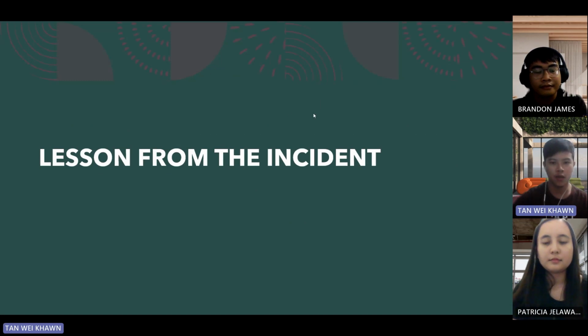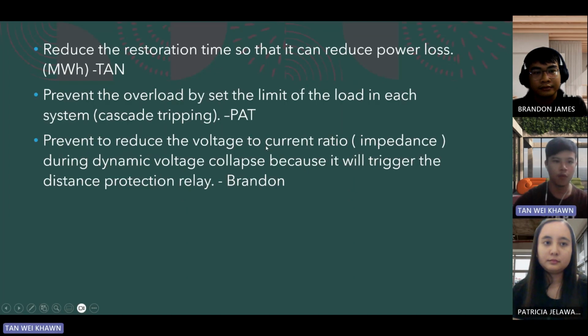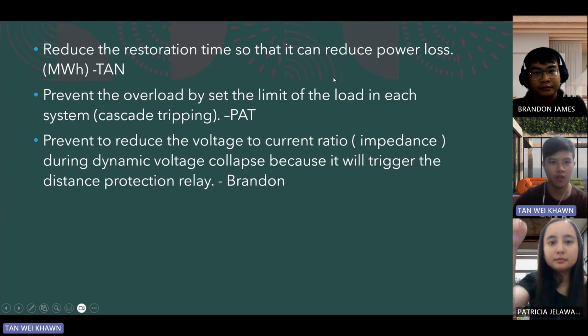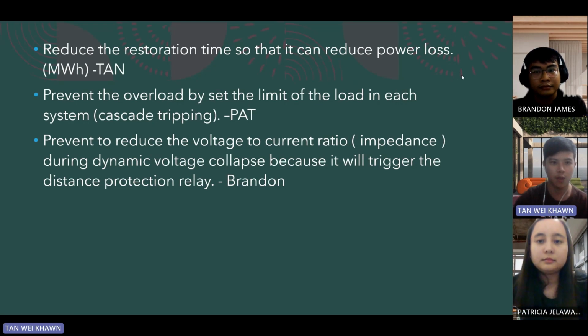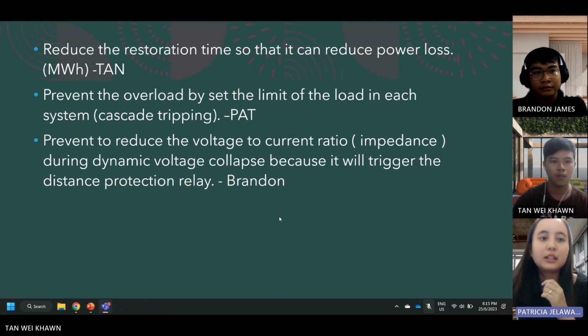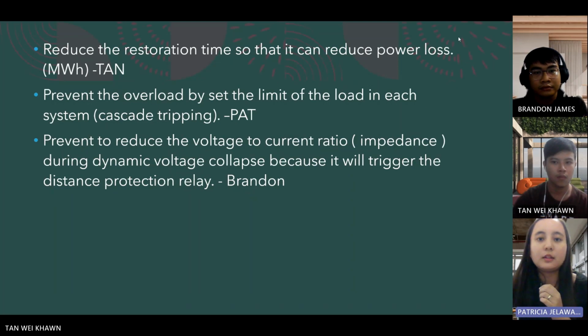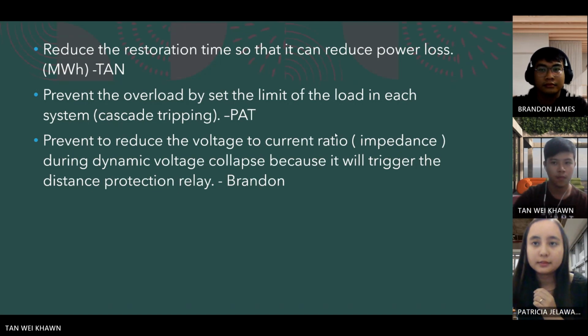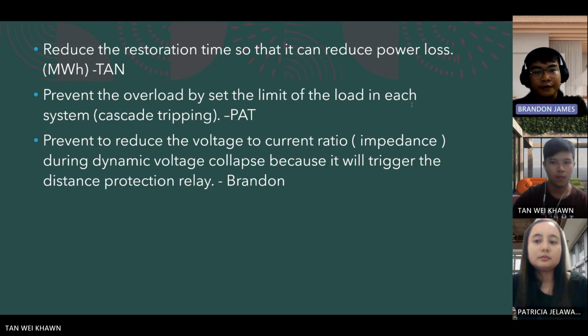Okay, the lesson from this incident, for me, is to reduce the restoration time so that it can reduce power loss in megawatt hour. As for me, we can prevent overload by setting the limit of the load in each system, so considering the cascade tripping. For mine, it is to prevent the reduction of the voltage to current ratio, impedance, during dynamic voltage collapse because it will trigger the distance protection relay.